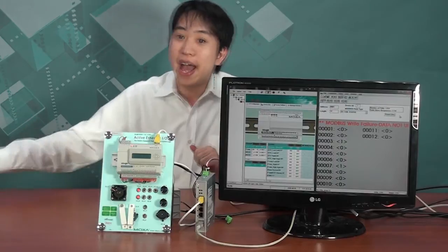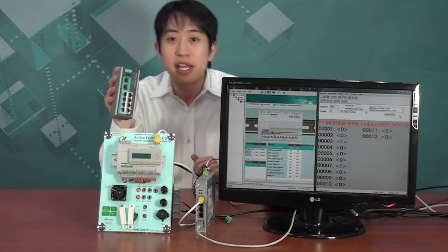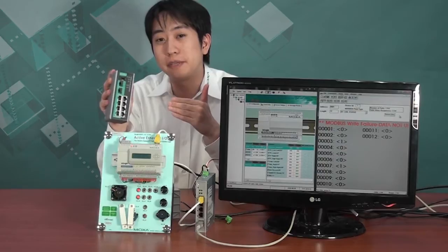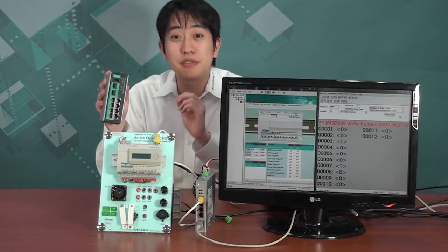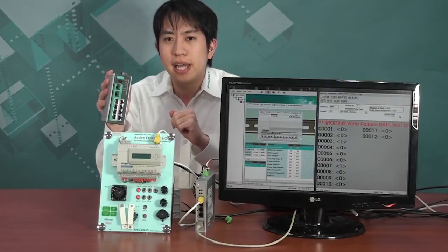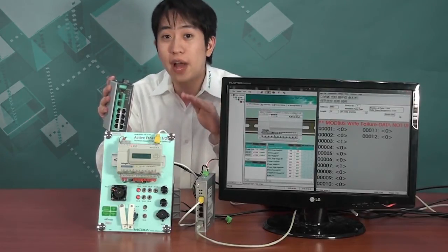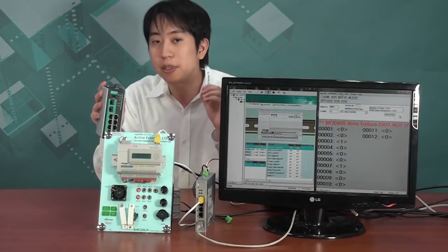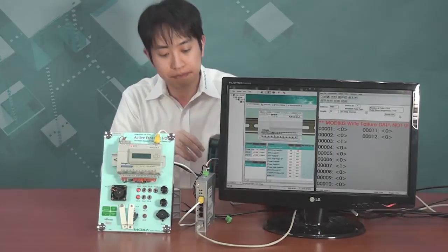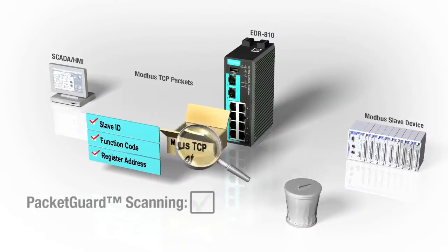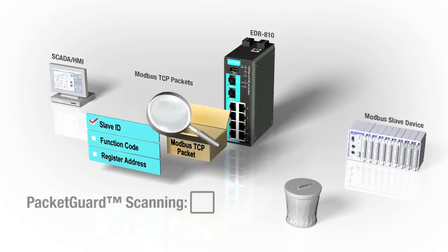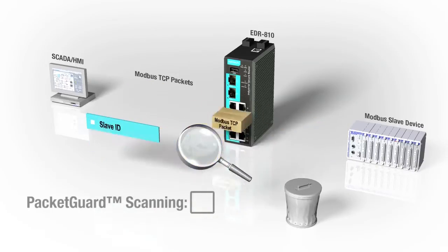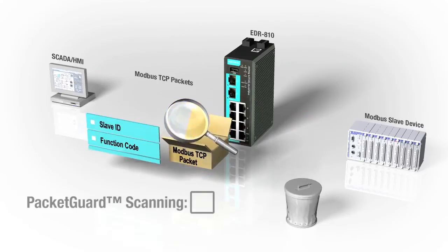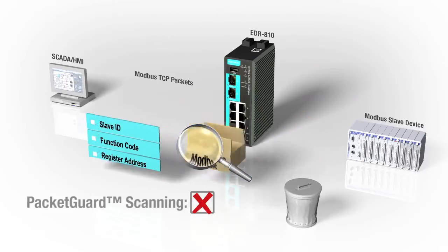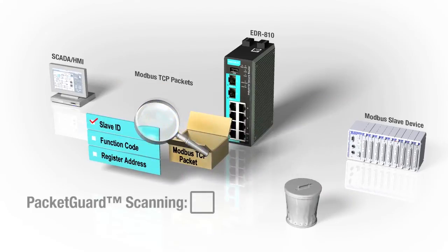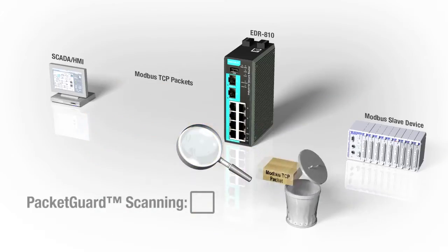Let's fix this by adding the EDR-810. An industrial secure multi-port router. Now, the EDR-810 has a built-in firewall and VPN functionality. And critically for industrial networks, it also adds deep scanning of industrial Modbus packets, what we're calling PacketGuard. PacketGuard performs deep inspection of every individual Modbus TCP packet and verifies its slave ID, function code, and register address. Modbus packets that do not meet its requirements are dropped. This adds one more layer of protection on the application level to an existing firewall.